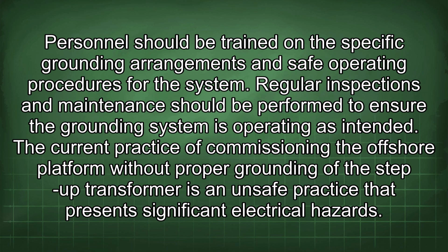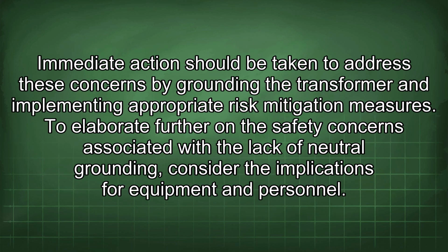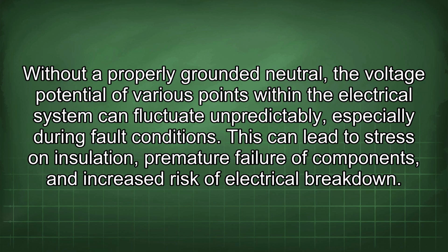The current practice of commissioning the offshore platform without proper grounding of the step-up transformer is an unsafe practice that presents significant electrical hazards. Immediate action should be taken to address these concerns by grounding the transformer and implementing appropriate risk mitigation measures. To elaborate further on the safety concerns associated with the lack of neutral grounding, consider the implications for equipment and personnel. Without a properly grounded neutral, the voltage potential of various points within the electrical system can fluctuate unpredictably, especially during fault conditions.